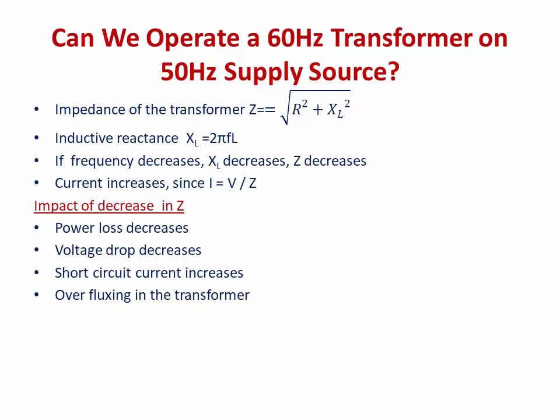There will be power loss decreases and voltage drop decreases — both are very good signs. But look at the other two effects: short circuit current increases, and over-fluxing occurs in the transformer. These last two parameters — short circuit current and over-fluxing — play a very important role in deciding whether a 60 Hz transformer can be used on a 50 Hz supply.